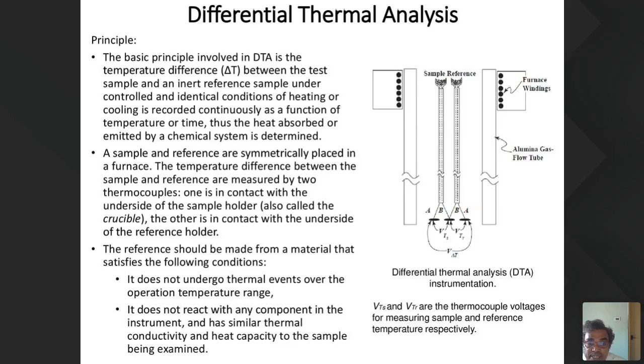In differential thermal analysis, the basic principle is the temperature difference. A sample and a reference sample are placed in a furnace. The temperatures of the sample and the reference are measured by two thermocouples. One is in contact with the underside of the sample holder, the other with the underside of the reference holder. The reference should be made from a material that does not undergo thermal events over the operating thermal range, does not react with any component in the instrument, and has similar thermal conductivity and heat capacity to the sample being examined.